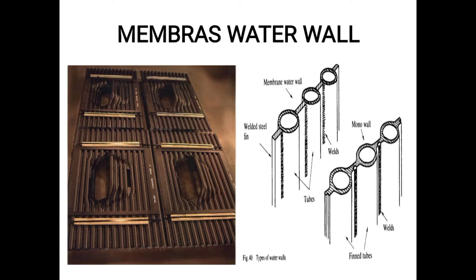To prevent this, we use membrane water walls. In a membrane water wall, the gap between two tubes is filled by a plate — as seen in the sketch and real picture, the gaps between the tubes are completely filled with a plate, preventing clinker and corrosion buildup.